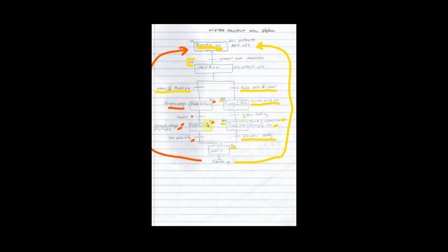And so this approach is much more stable, and it's always good to map your process out anyway, so you have a good understanding of how it progresses, right? So if the project said something like there was a reset button, if I press the reset button from any state, maybe I want to go to power up. So I could easily pencil that in as a backwards arrow that would take me back to power up. So making changes to your process is very simple with state diagrams if you start out with that in mind.